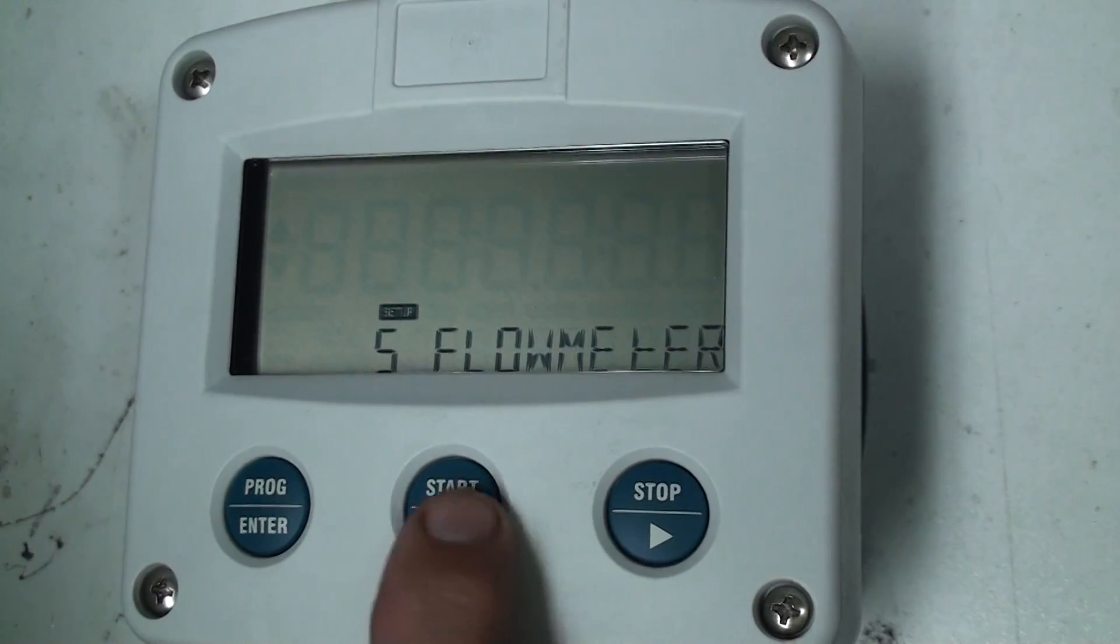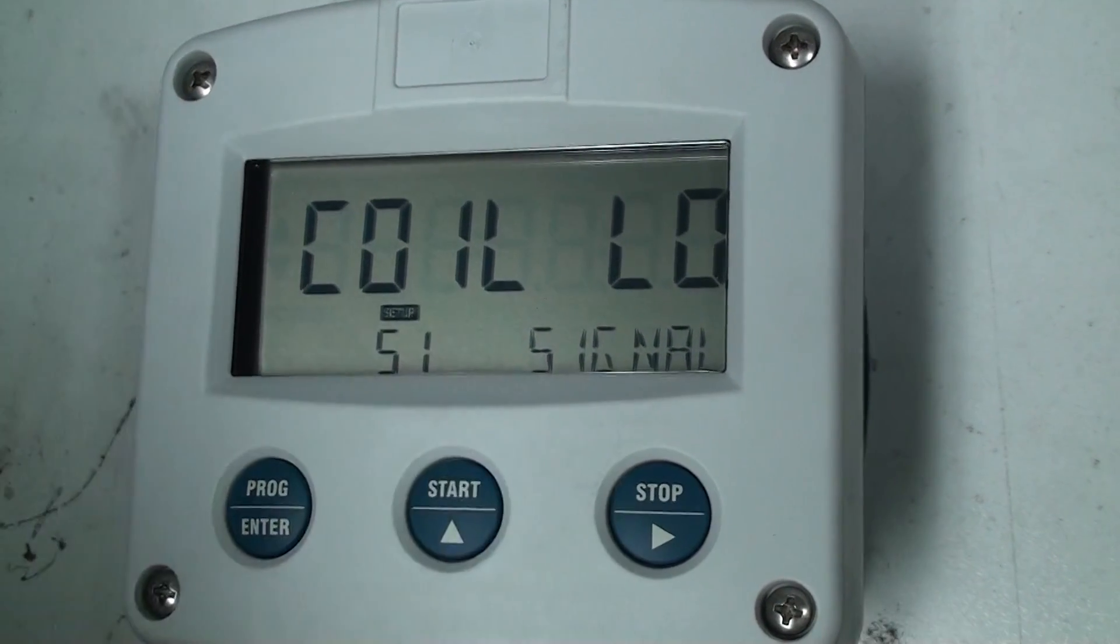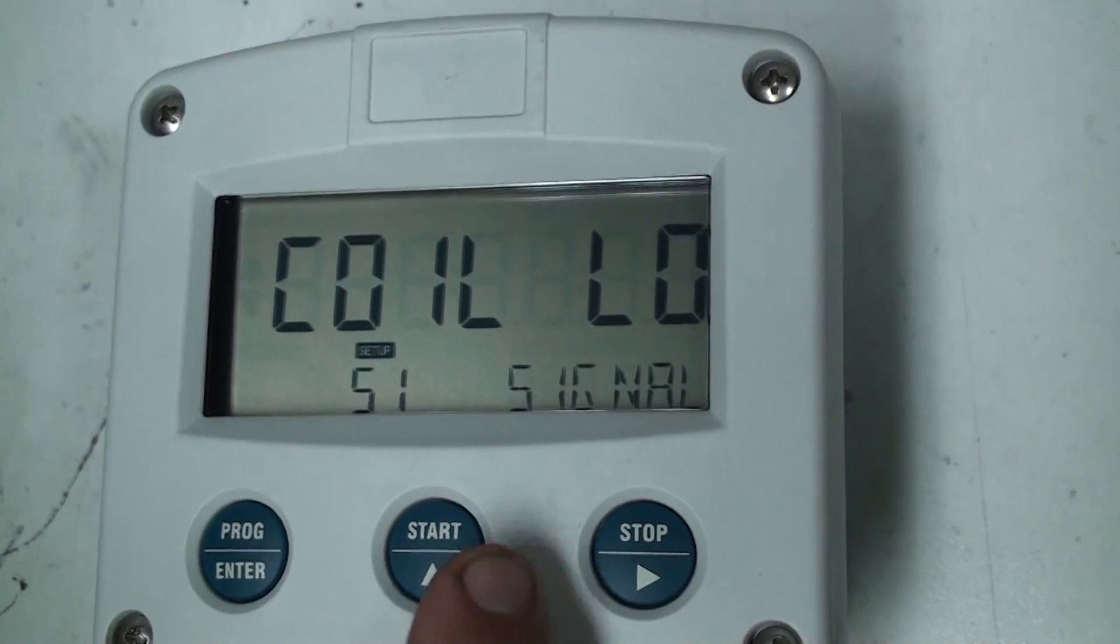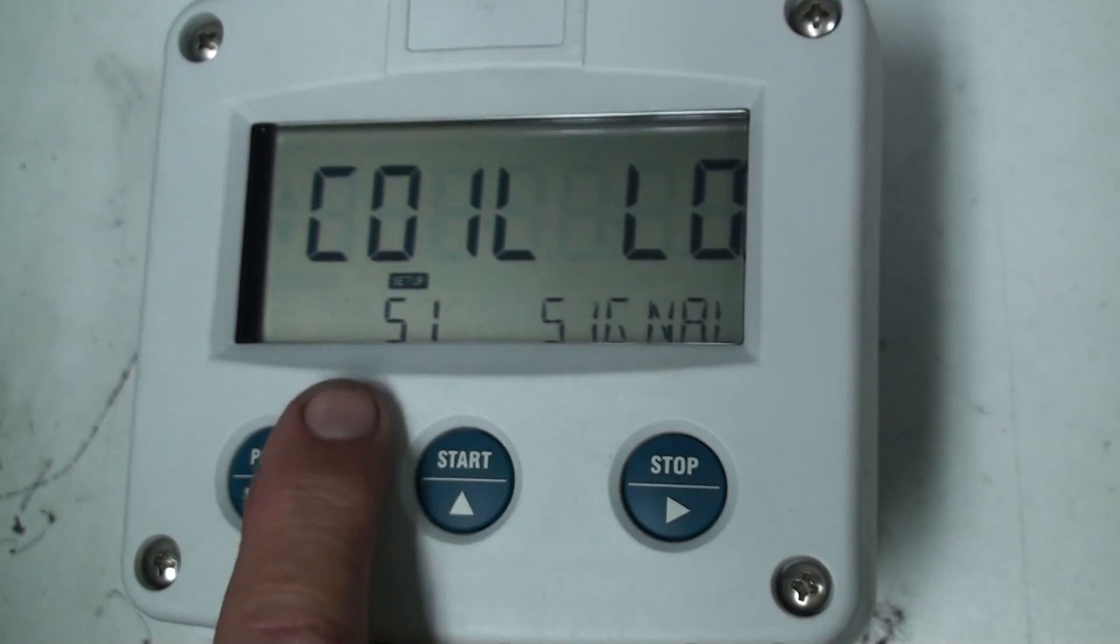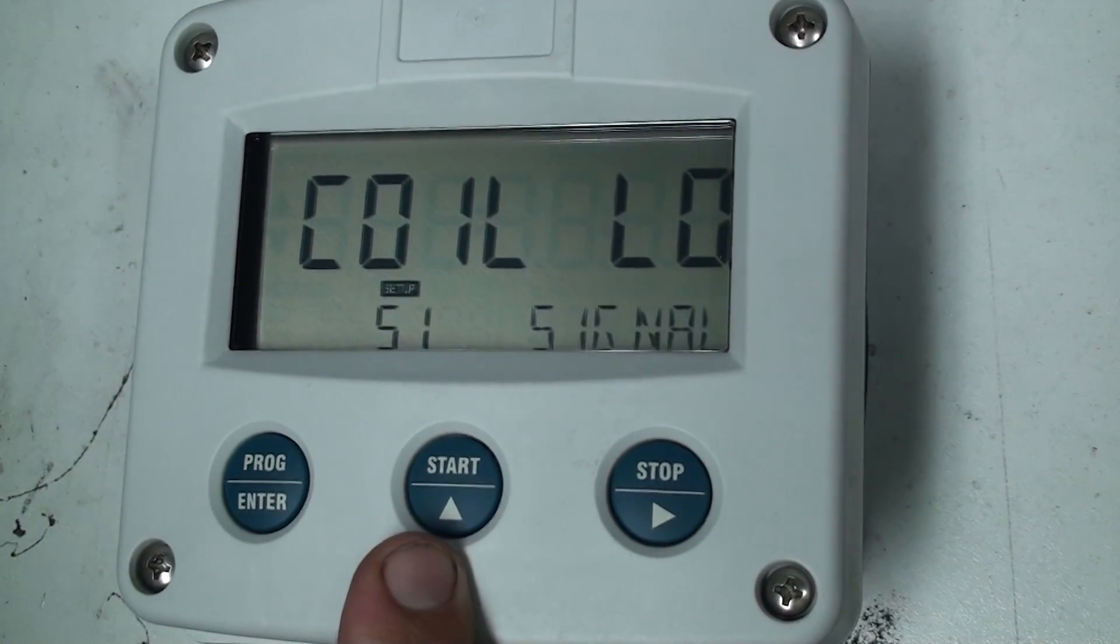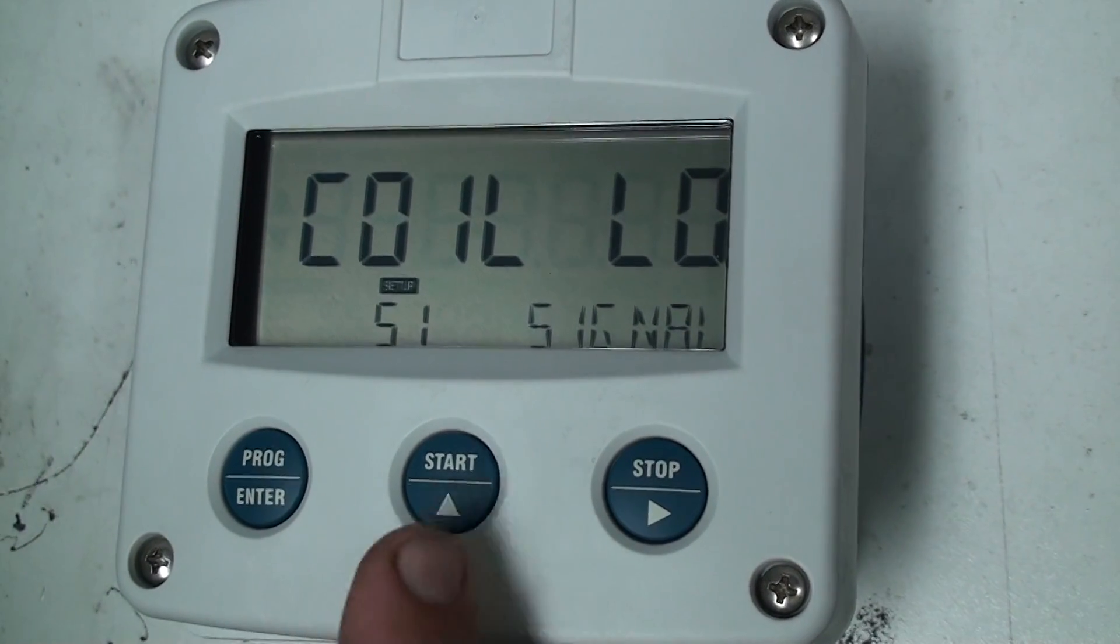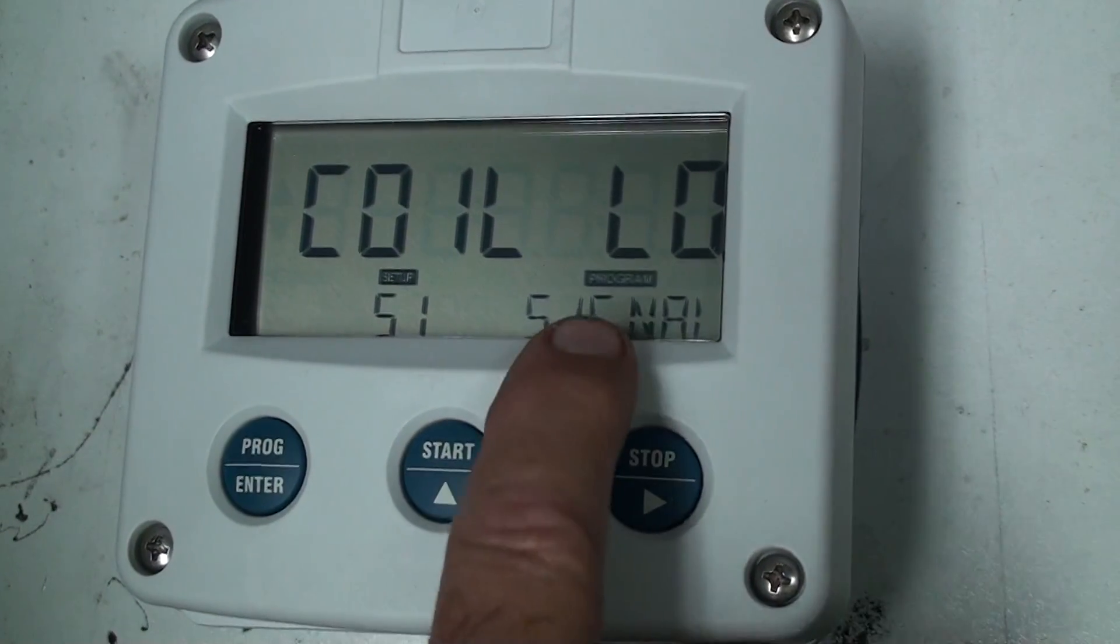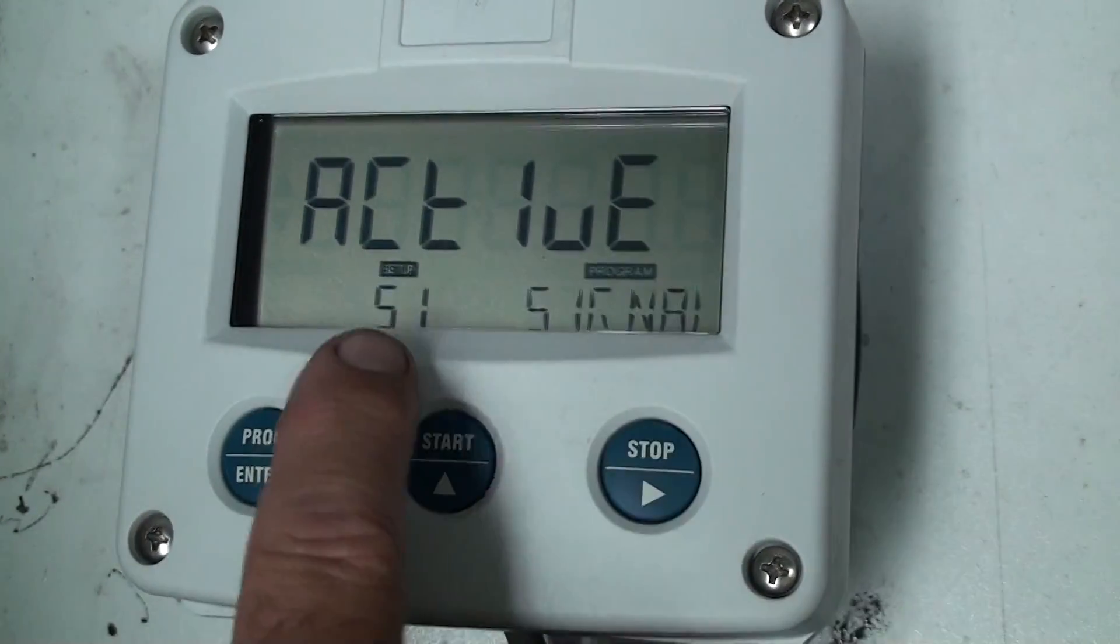We'll go to chapter 5. Chapter 5 is for the flow meter. Chapter 5.1 is for the signal. Now this is the pulses that you're going to receive from your flow meter to this controller to how you're going to read your flow rate. At the moment it's set for a coil on a low pulse. So we need to change that to if it's a hall sensor you'll need NPN, if it's a reed switch you'll need a reed. So I'm going to program it for a reed switch. I press my program button and you'll see the program start to flash. I will cycle through all the options.